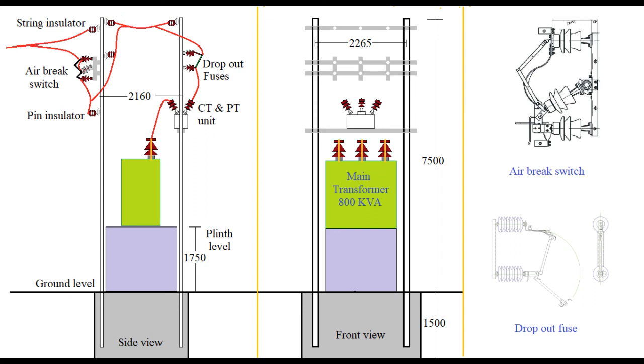When supply reaches the inner portion of overhead lines between the 2 pairs of poles, we may connect conductors from these overhead lines to dropout fuses fitted from outside of the pole structure. It may be noted that the overhead conductors within the 2 pairs of poles are connected through string insulators. Further, jumpers connect these overhead lines with one end of the dropout fuses, and the other end of the dropout fuses connects to the CT and PT unit. Finally, conductors pass from the CT-PT unit to the HT side of the main transformer. It may be noted from the diagram on screen that the transformer is plinth mounted and placed within the rectangular portion marked by 4 poles.